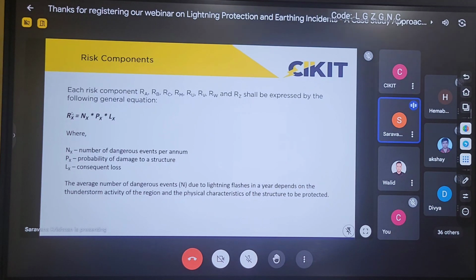The number of dangerous events also depends upon the dimensions of the building. For example, everyone knows that if the height of the building is much higher, or if my structure is the tallest structure in that particular locality, then obviously the risk due to lightning on my building will be higher.